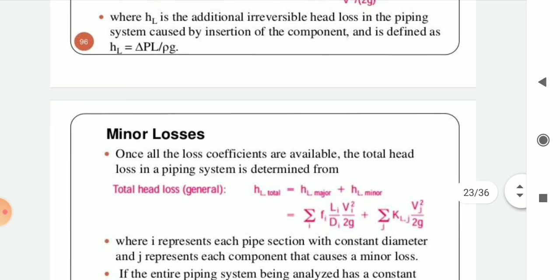So once all the loss coefficients are available, the total head loss in a piping system is determined from HL total = HL major + HL minor. That is, the summation of fi Li Vi² divided by Di 2g, plus the summation of KLj Vj² divided by 2g, where i represents each pipe section with constant diameter and j represents each component that causes a minor loss.